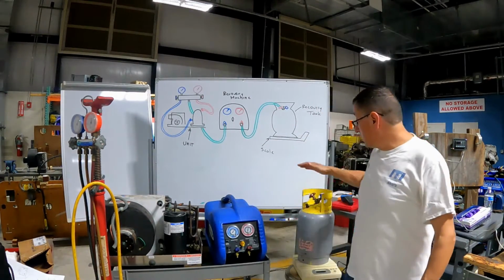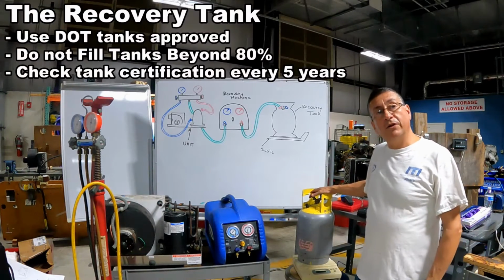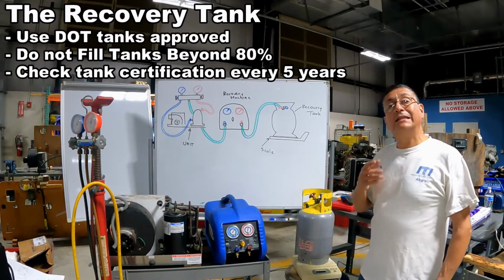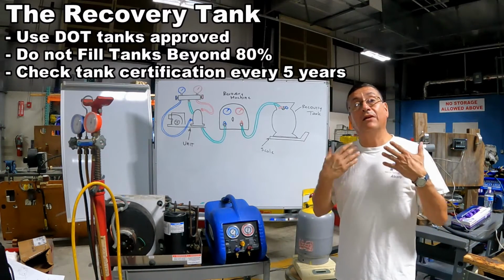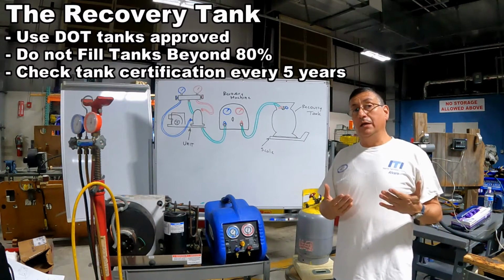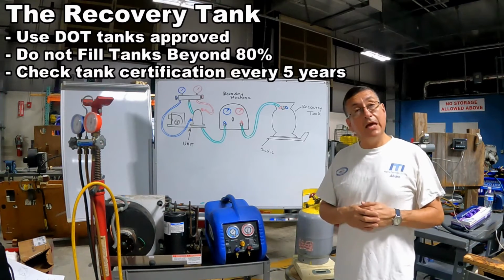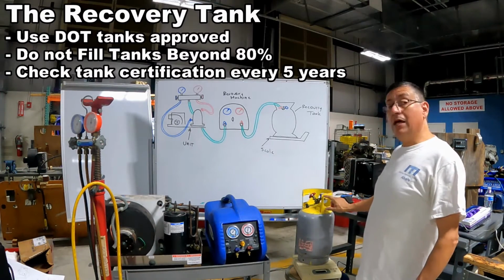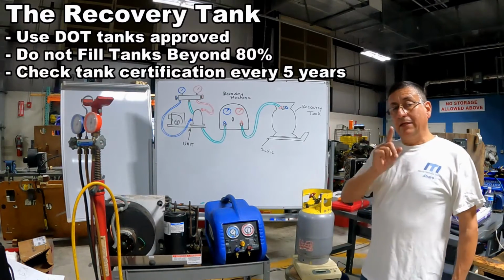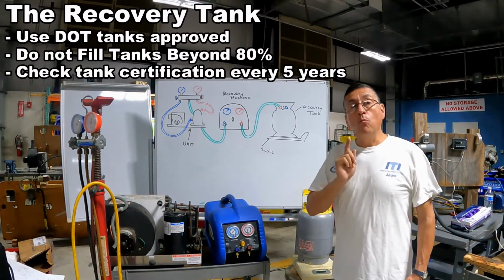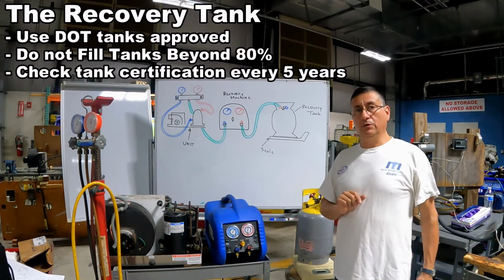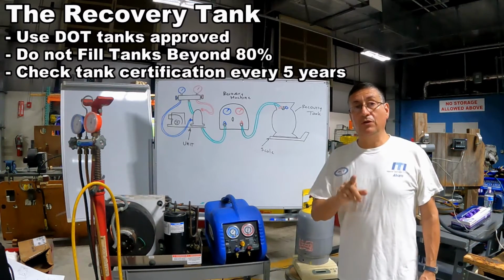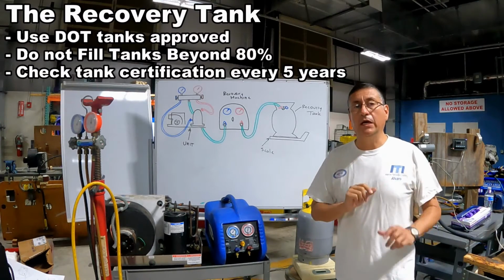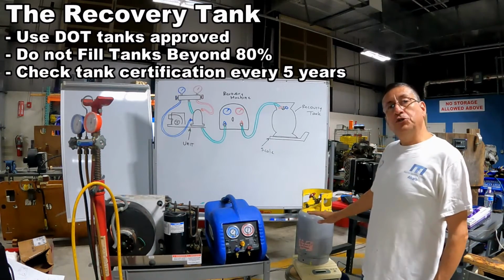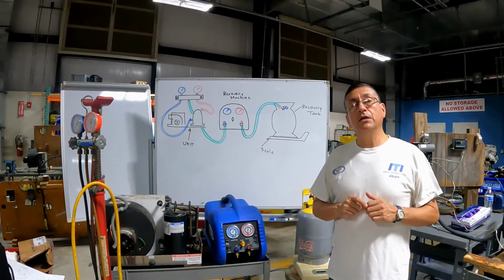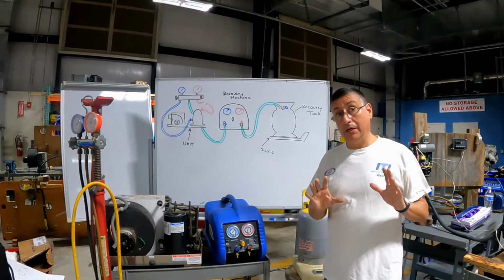Okay, and we need a special tank to recover the refrigerant. Remember that there are tanks according to the refrigerant. For example, if the refrigerant is 410A, you need a tank with the label 400. Remember that the tank should be filled no more than 80%. This is another EPA question in the EPA certification that we are going to take. Yes, never charge the recovery cylinder more than 80%. This is a critical point.